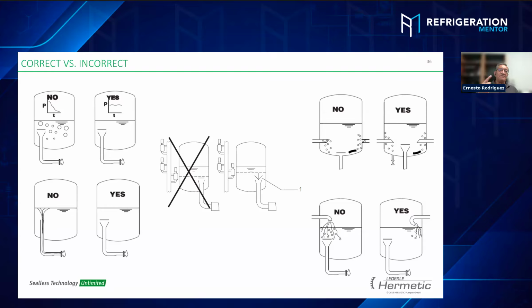That means problem number one, flash gas. Problem number two, you lose the balance in your system. That is the big thing. We need to balance out the whole system to make sure that all the flow is happening simultaneously and correctly, even if there's defrost, no defrost, and as we continue to move that CO2. That's correct.